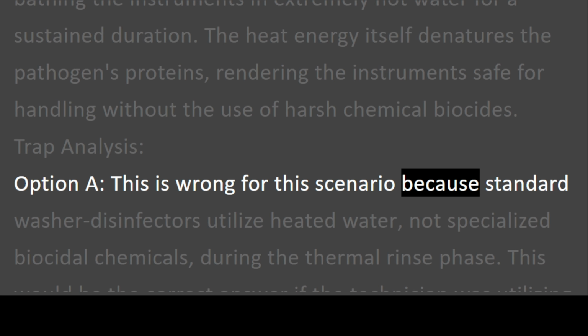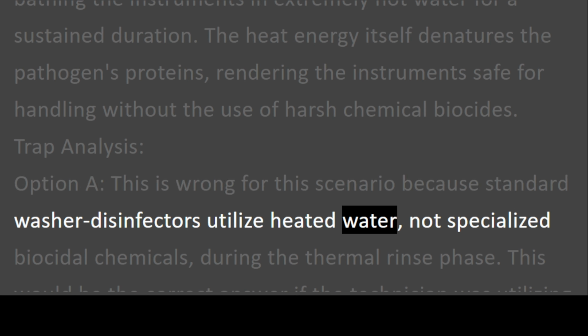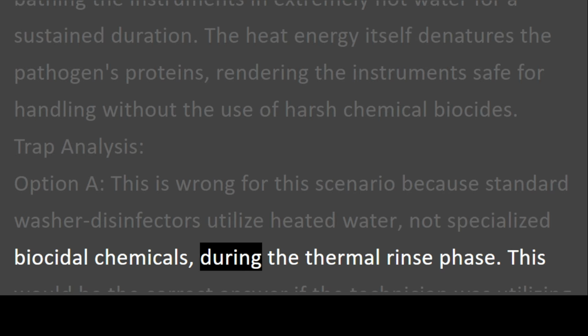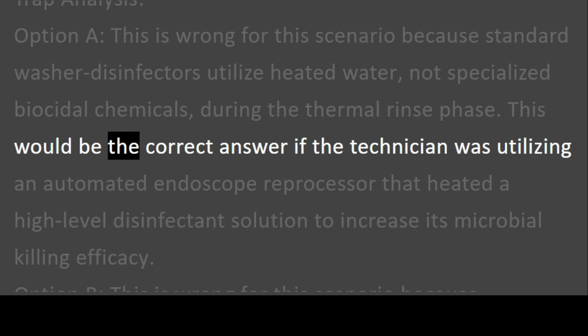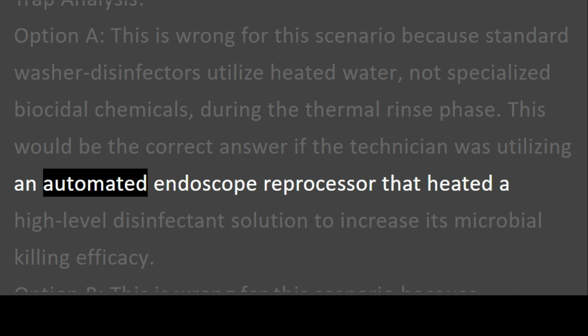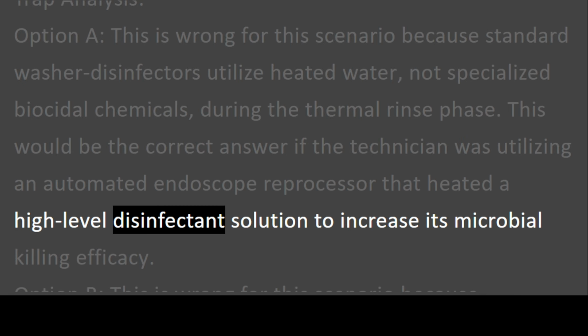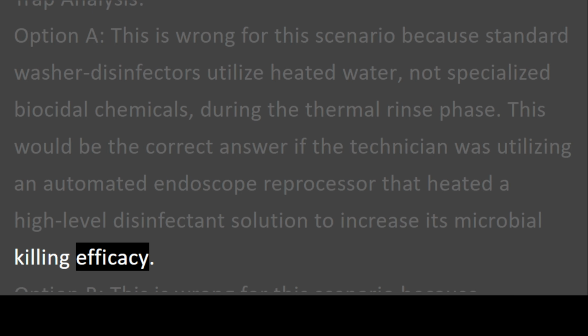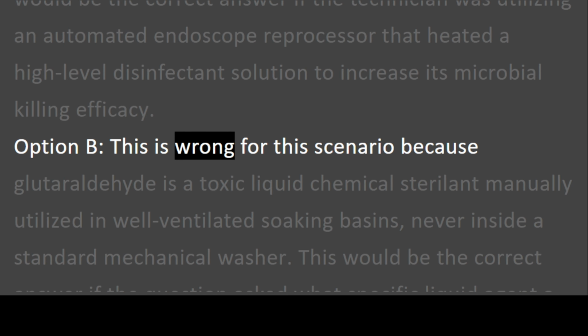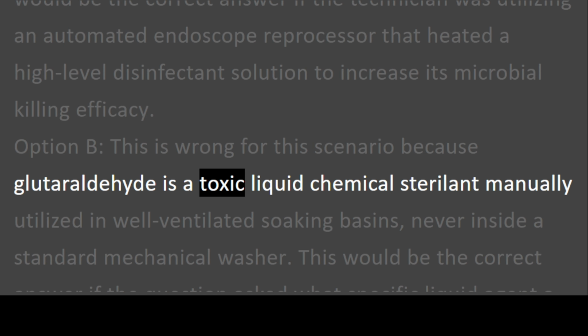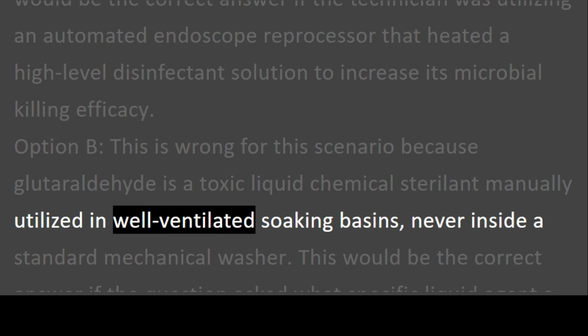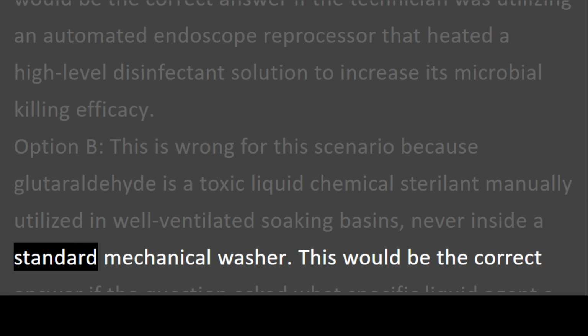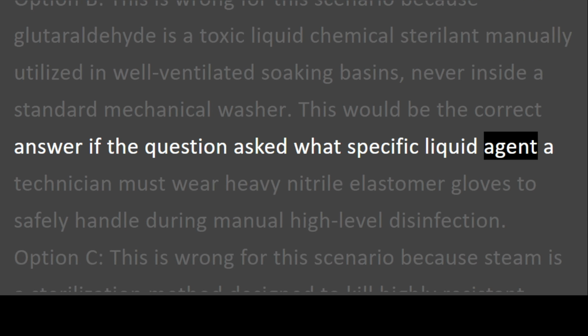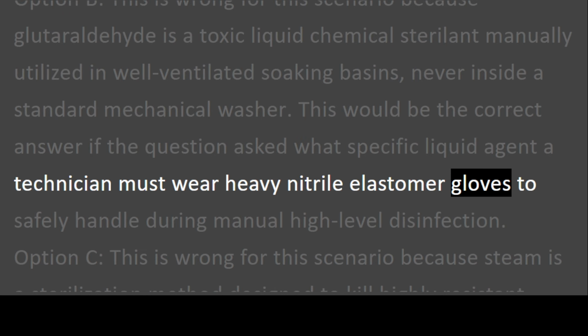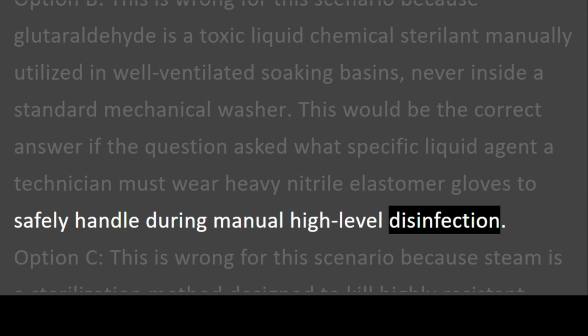This is wrong for this scenario because standard washer disinfectors utilize heated water, not specialized biocidal chemicals, during the thermal rinse phase. This would be the correct answer if the technician was utilizing an automated endoscope reprocessor that heated a high-level disinfectant solution to increase its microbial killing efficacy. Option B. This is wrong for this scenario because glutaraldehyde is a toxic liquid chemical sterilant manually utilized in well-ventilated soaking basins, never inside a standard mechanical washer. This would be the correct answer if the question asked what specific liquid agent a technician must wear heavy nitrile elastomer gloves to safely handle during manual high-level disinfection.